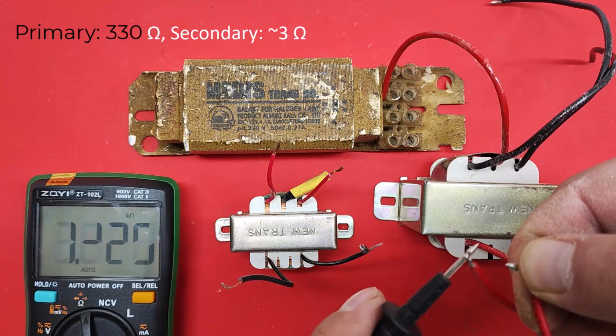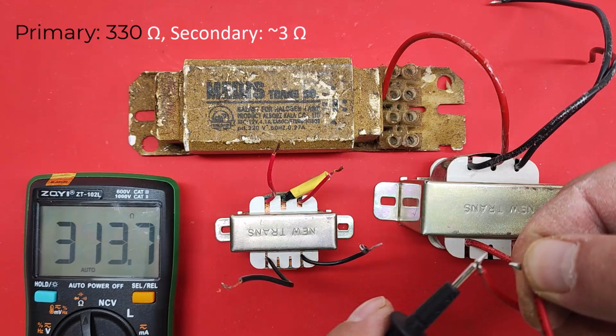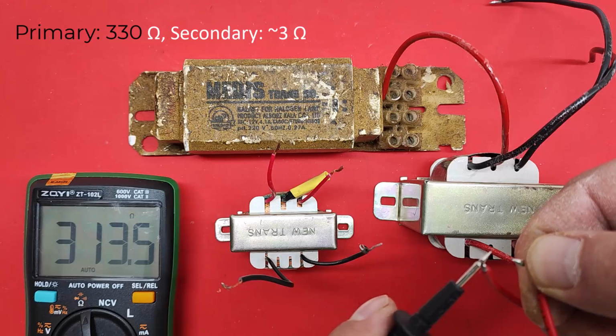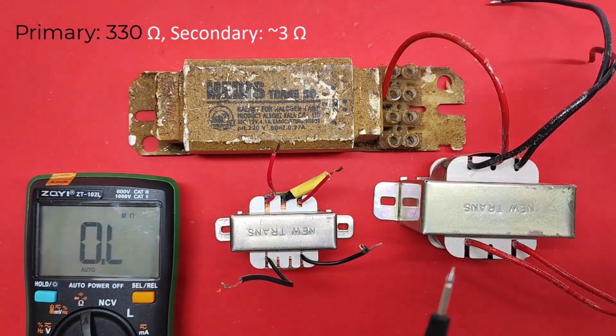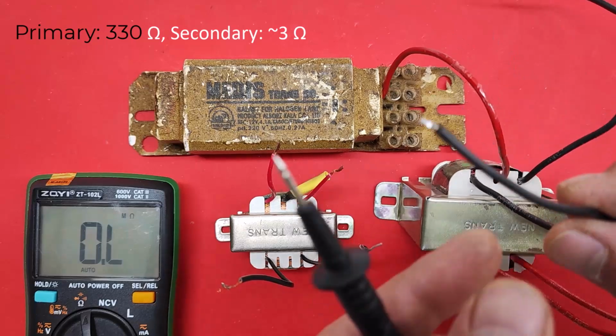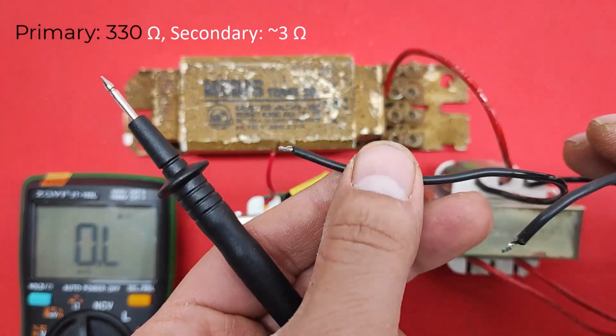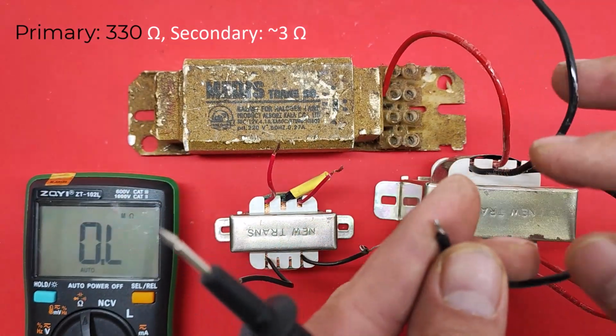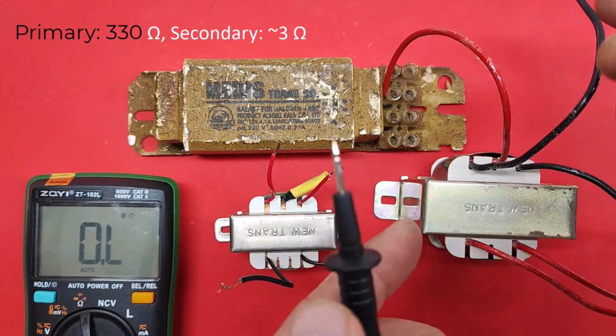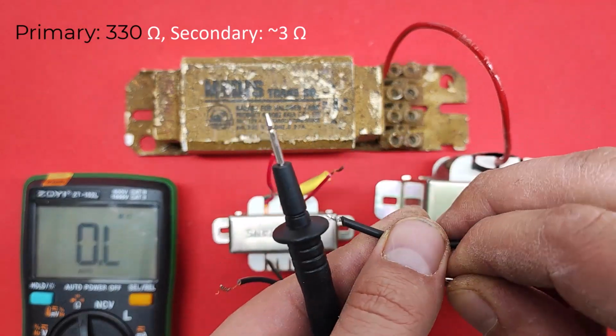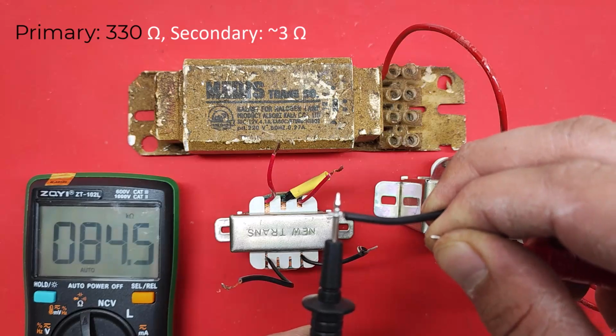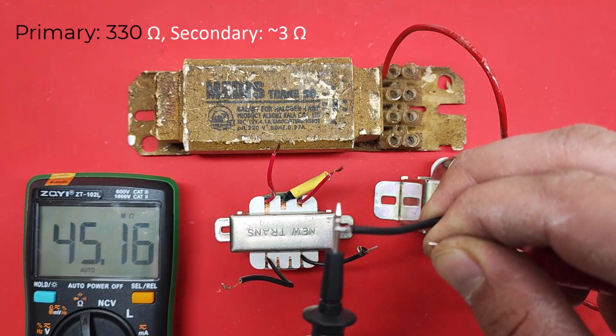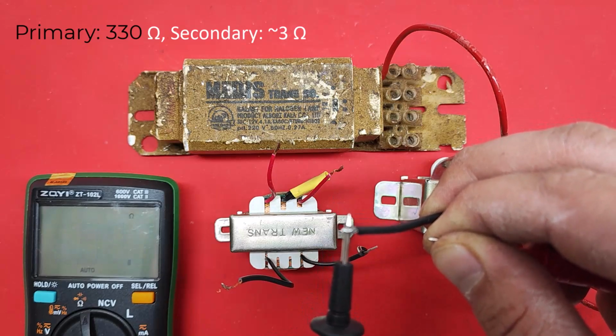The biggest advantage of resistance testing is safety. You can identify transformer windings without applying mains voltage. It's also quick and requires only a multimeter. The drawback is that resistance values alone cannot determine the exact voltage or power rating. For accurate results, voltage testing is still necessary.